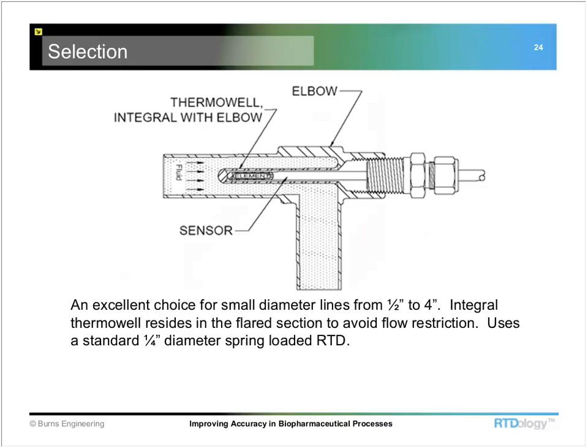One of the concerns is that, especially with biopharm processes, we're introducing another material into this process, and if something should break internally, you have that material getting inside of your system, and it could be a real big problem to clean it out of there. Whereas if you just have stainless parts and something goes to heck on you, it's still a problem, but it's not as big as if we have some semi-unknown heat transfer paste that you have to start cleaning out of the whole system.